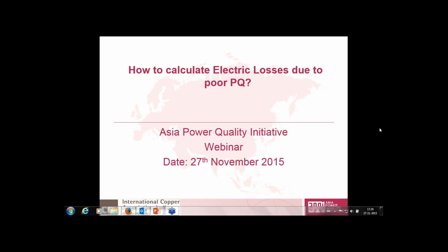But if I correctly remember, for lighting systems, I think they had some limit on the total harmonic distortion as well as on power factor. So there is a regulation on power factor, of course, where typically a penalty is there. If I'm correct, I think some of the utilities put a penalty if the power factor goes below 0.85. But yesterday we were in some discussion where a power factor above 0.9 is recommended. The question is, if there is a penalty, then you have to improve. If there is no penalty, then you may not get an incentive to improve it. So this is the situation at the moment, but we don't have any such standard on harmonics or power factor, as maybe in North America or Europe. That is as far as my knowledge goes.